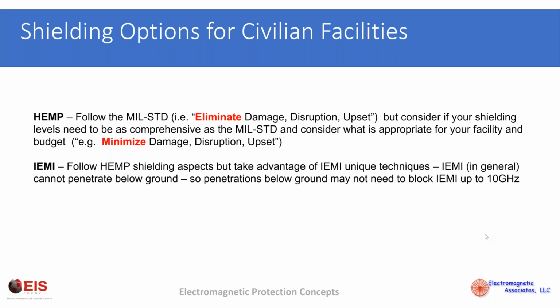So basically, for civilian facilities, the MIL standard is important to follow. It focuses on eliminating damage, disruption, and upset. But if your facility doesn't need to be quite as robust as a MIL standard time-urgent facility, you might want to adjust your standards and possibly look at a minimized damage, disruption, upset type of posture. That's a pretty deep technical discussion on the difference, but it's something to look at. And in IEMI, you follow HEMP shielding aspects, but also take advantage of some of the IEMI-unique techniques. Like, IEMI generally won't penetrate very far into the ground, so you can use techniques to shield against IEMI that are not possible with HEMP. Next slide, please.